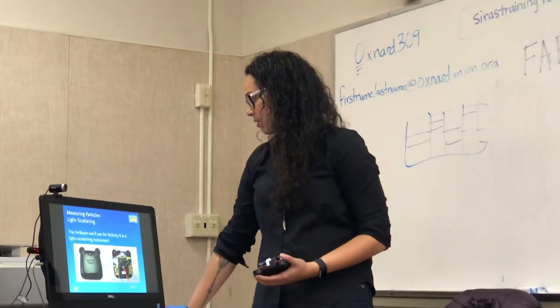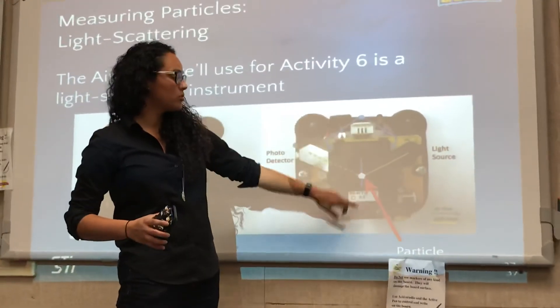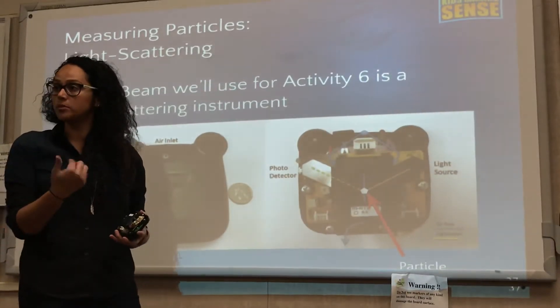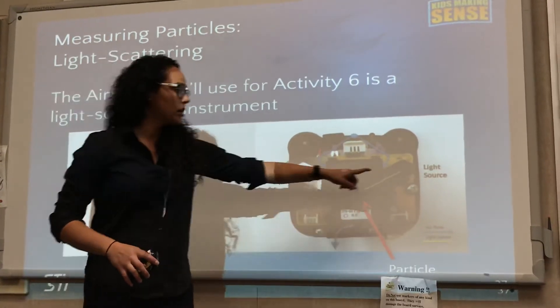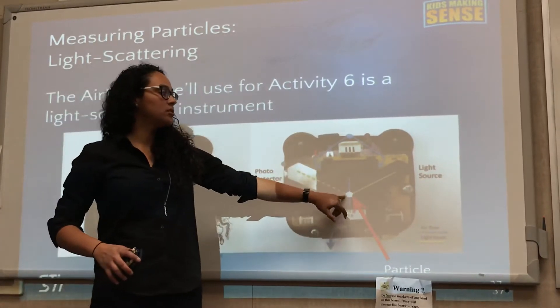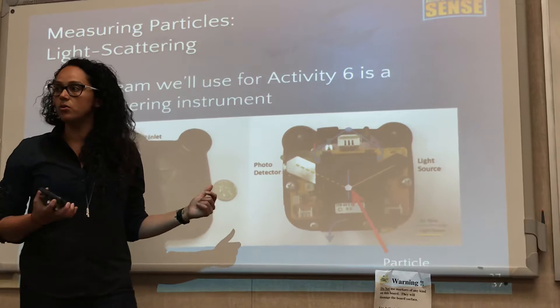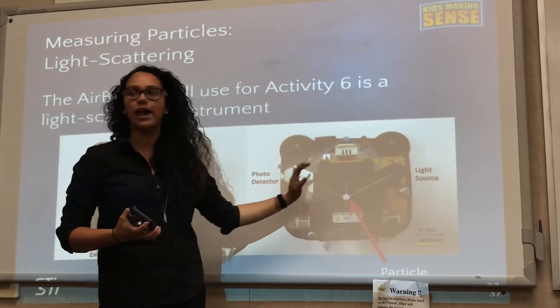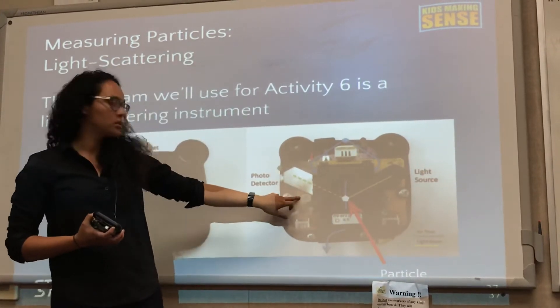Basically, this is going to work the same way. You're going to draw air through, except instead of collecting onto a piece of filter paper, you have a continuous light source going through, and then a kind of chamber where the particles can pass through using a fan — instead of a pump circulating the air. You've got a light source and then a photo detector, and essentially what this does is measure the scattering. Particles scatter light, so the more particles you have in there, the more scattering you can get, and that's what this detector is going to measure.